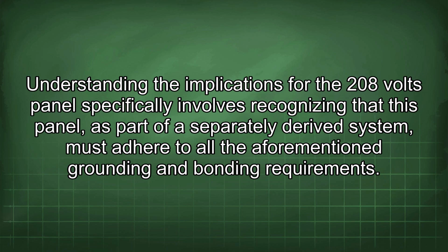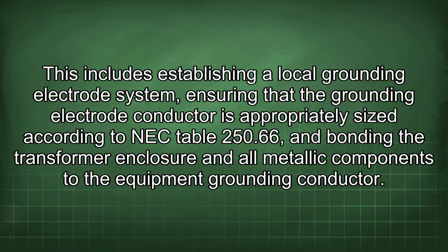Understanding the implications for the 208 volts panel specifically involves recognizing that this panel, as part of a separately derived system, must adhere to all the aforementioned grounding and bonding requirements. This includes establishing a local grounding electrode system, ensuring that the grounding electrode conductor is appropriately sized according to NEC Table 250.66, and bonding the transformer enclosure and all metallic components to the equipment grounding conductor.